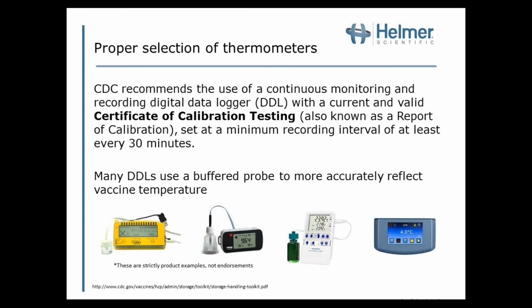And then another really important aspect is using a buffered probe. You can see the 3 thermometers on the left all show a buffered probe, which means that the probe is actually suspended, usually in glycol, and in doing so it more accurately reflects the temperature inside of the vial. On the right-hand side, one thing I wanted to bring up is many medical grade refrigerators do include a built-in thermometer that conforms to all of this. So it does have a buffered probe. It's a probe that is built into the refrigerator, and it will record automatically for you with downloadable reports. Oftentimes that's available with pharmaceutical grade units. But regardless, this is the minimum for a thermometer.